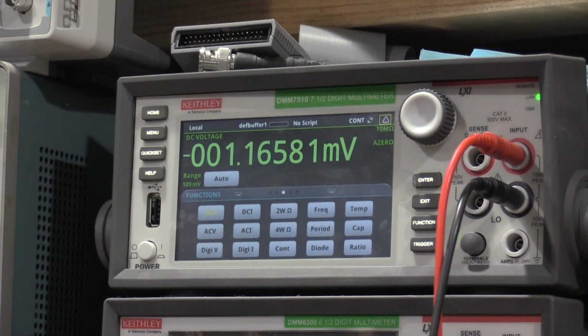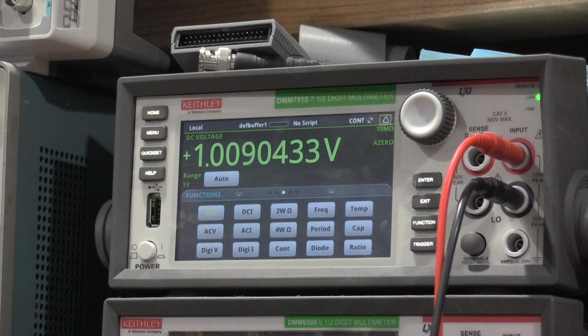We need to hook up the output of the DC amplifier to the very sensitive meter. And then we need to apply 1 volt to the front end of the DMM. So let me set that up real fast. And we are way out on gain. So now what we need to do is zero the gain, and this should be done at 1 volt.